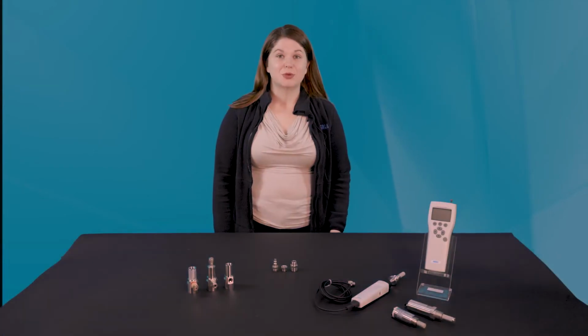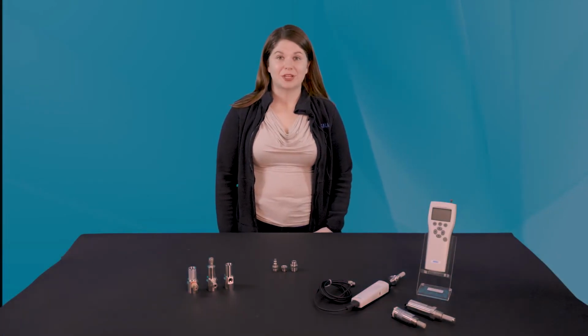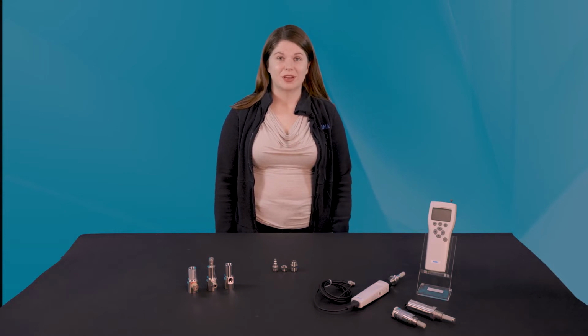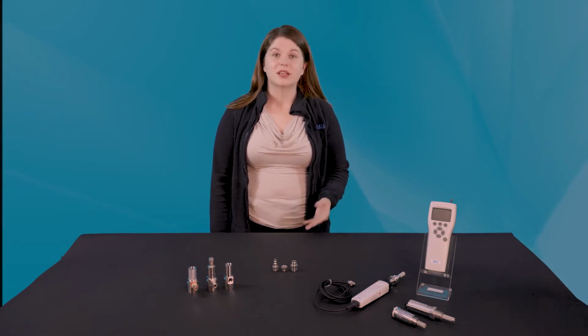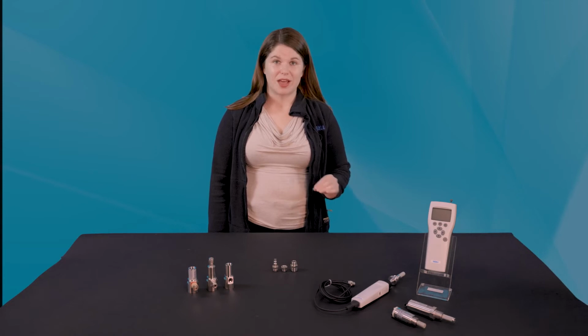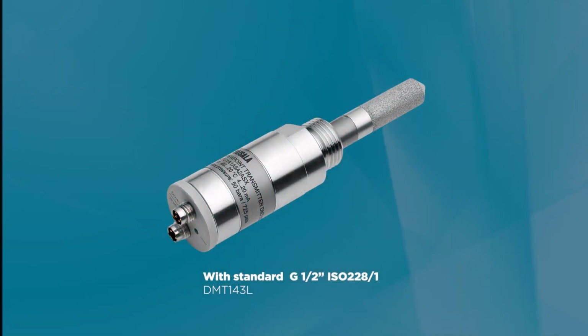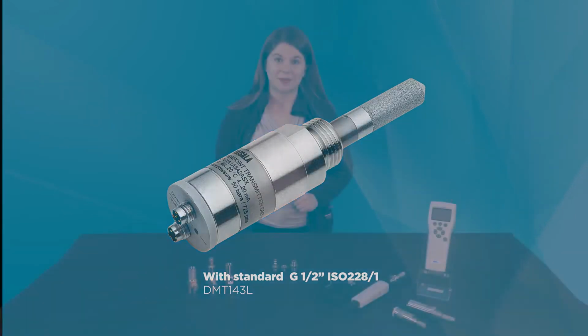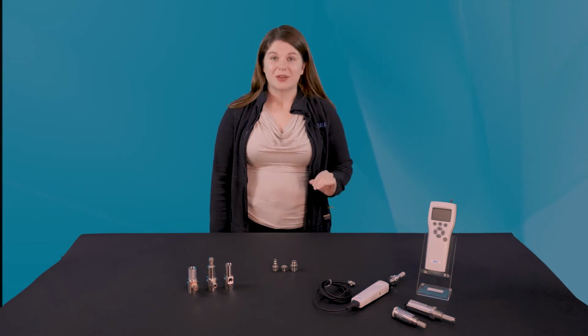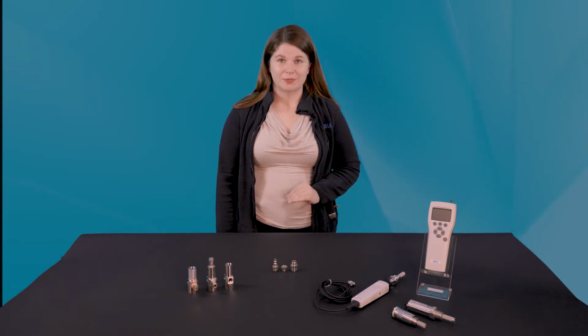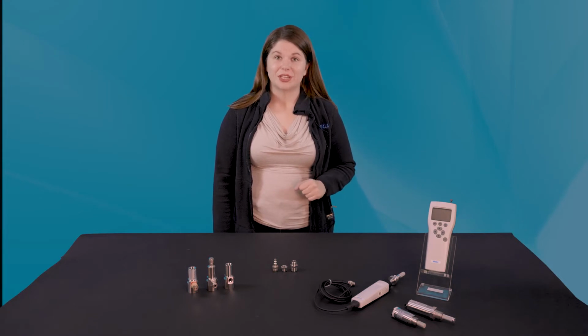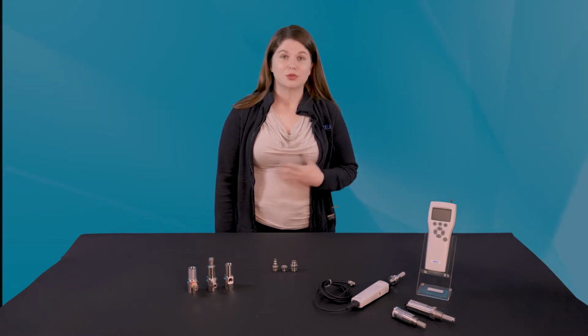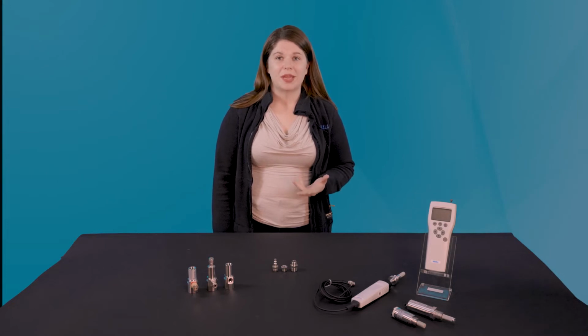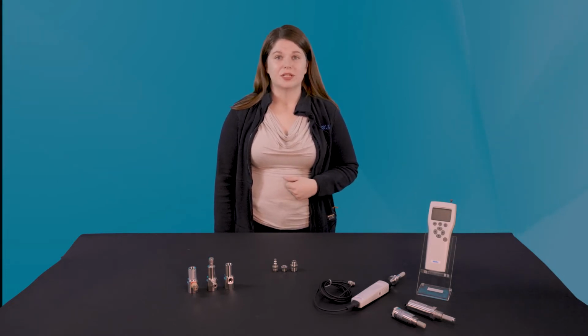All of Vaisala's dew point probes offer a standard 1/2-inch NPT or ISO threaded fitting body. Our sample cells are designed specifically to mate with the ISO 1/2-inch connection. So when ordering a transmitter, if you plan on using a Vaisala sample cell, you will need to select this ISO fitting body. The sample cells are not compatible with an NPT thread. The NPT process connection can be selected when installing the probe directly into a process or when mating with an NPT thread that is already installed.